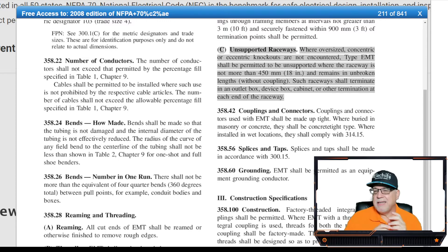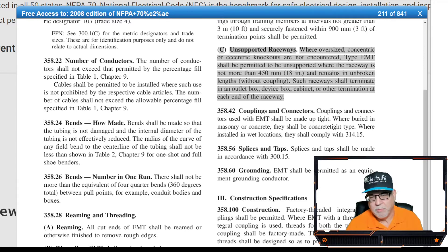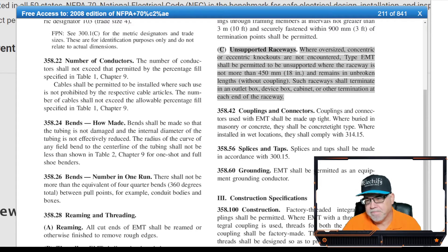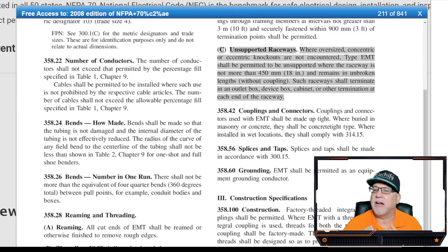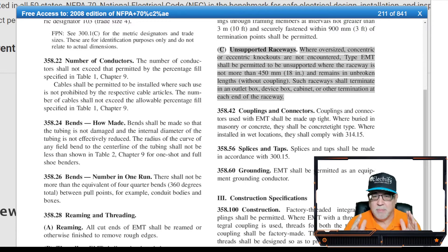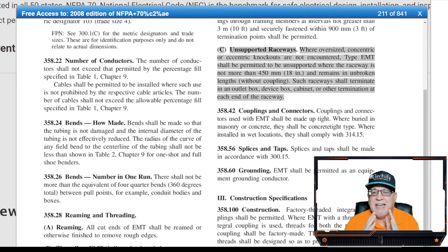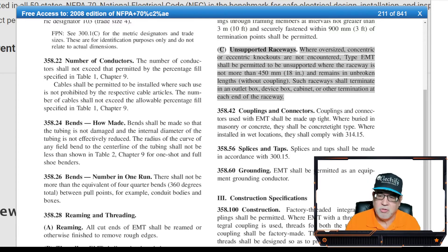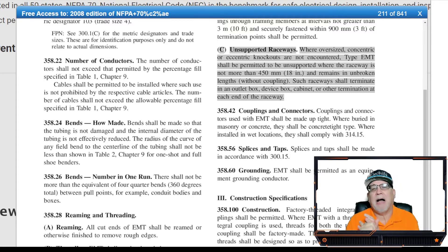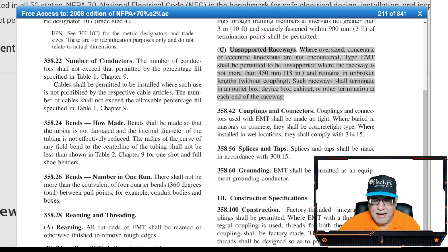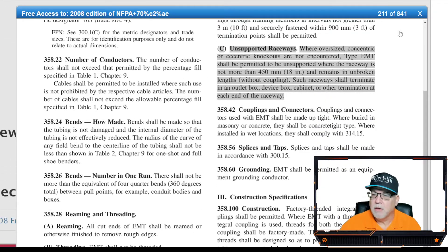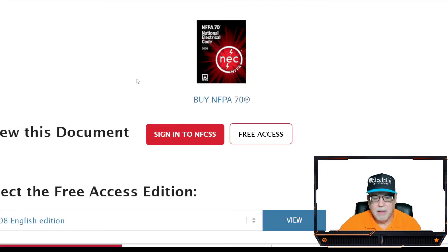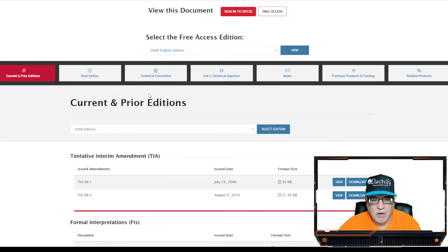358.30, you see the highlights. So these highlights are letting me know that there was a change for this edition, and that was the advent of C. What does C say? Here's C. It says where oversized, concentric or eccentric knockouts are not encountered, Type EMT shall be permitted to be unsupported where the raceway is not more than 18 inches and remains in unbroken lengths without coupling. Such raceways shall terminate at an outlet box, device box, cabinet or other termination at each end of the raceway. So in the 2008 edition, this was introduced. Now, we want to see why this was introduced.